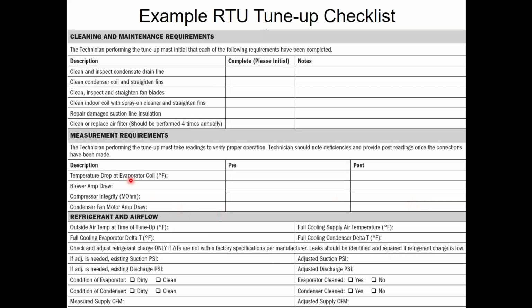The biggest thing to do is taking a temperature drop across the evaporator coil. This gives you an idea of how much cooling functionality you have, right? So if you have, whatever, an 80-degree inlet temperature and you have 58 coming out, you're getting 22 degrees done on that air temperature, right? And what are you getting done after you cool it? So you can start seeing those things. The temperature across the evaporator coil is an indicator of how much I've improved the cooling system by cleaning the coil. And then the blower amp draw, on a constant volume system, is an indicator of how much I've improved the airflow ability of that system. Right? And then I can do the same thing on the outdoor unit with that guy's amp draw.